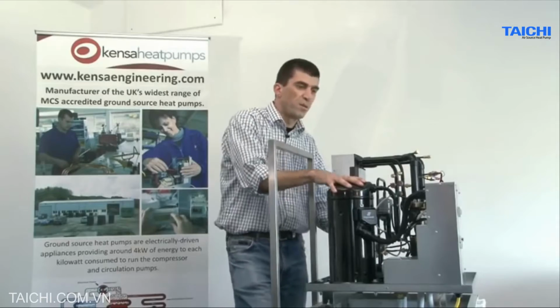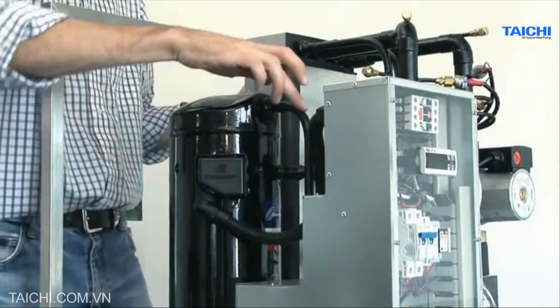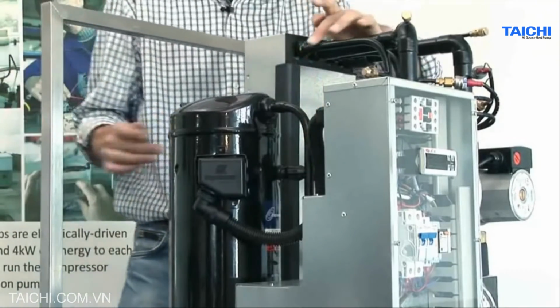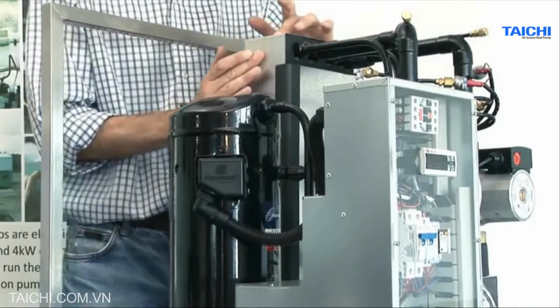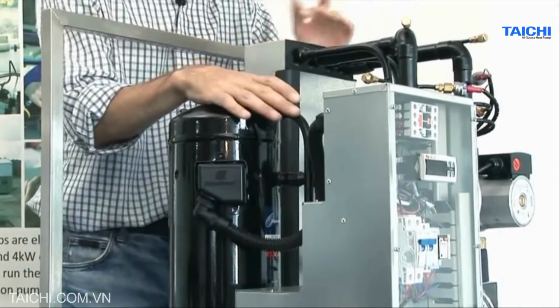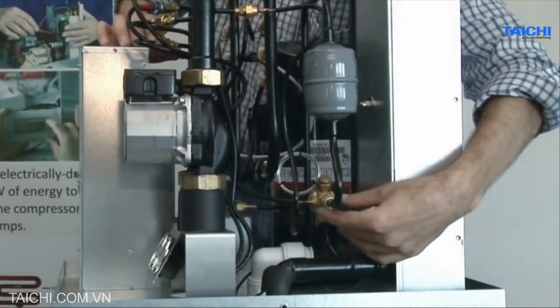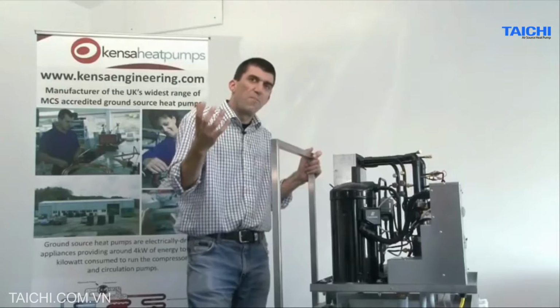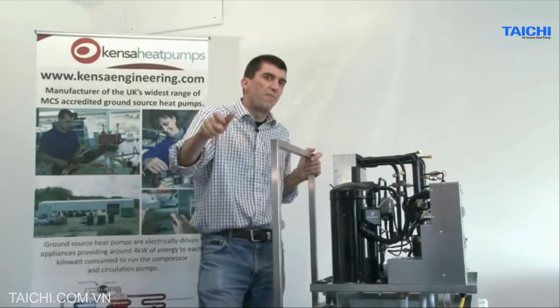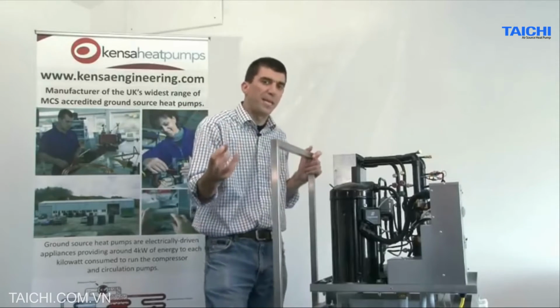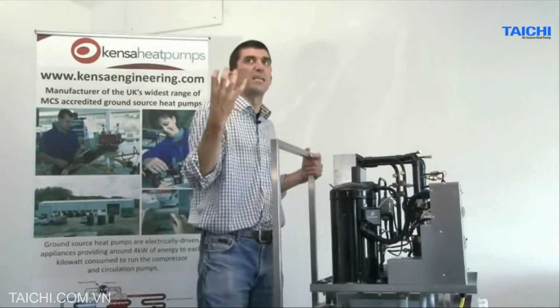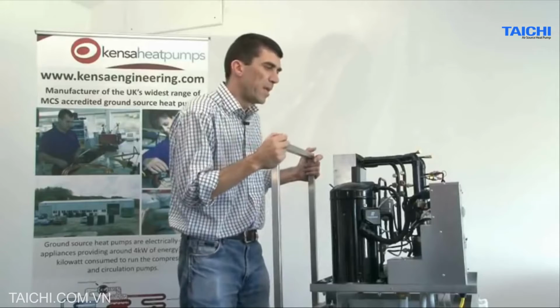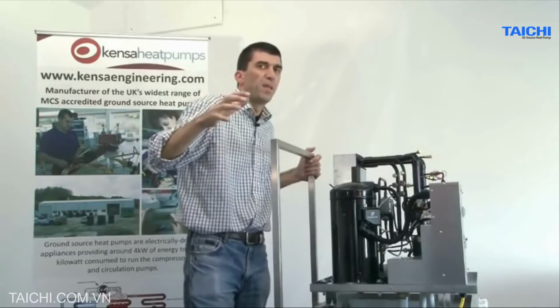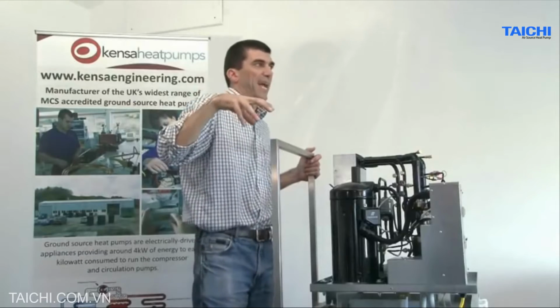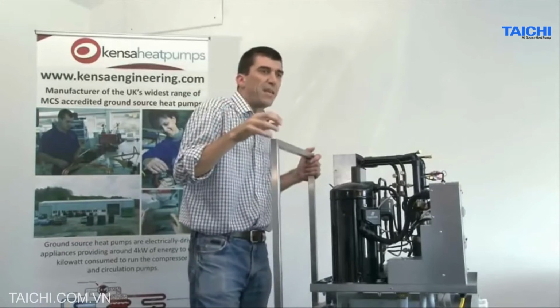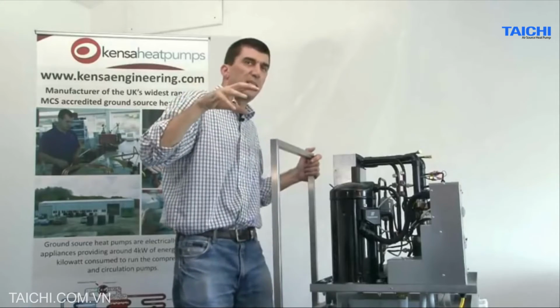Inside the high pressure side, which is the discharge side from the compressor, the gas comes out of this pipe here and passes into the condenser heat exchanger. It's held under high pressure in here by the restriction of the expansion valve and the pumping action of the compressor. With your bottle of camping gas or whatever it may be, when you open the valve, you're releasing the pressure. And what is actually happening inside that bottle is the liquid is changing state. It's boiling into a vapor. But that process is a two-way street. When they make the bottle of Calor gas or whatever it is, they actually pump the gas in and the vapor condenses into a liquid.